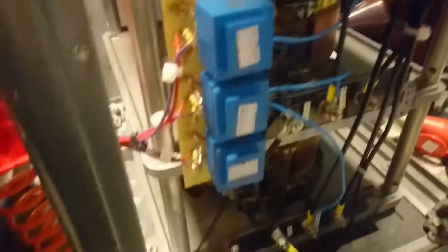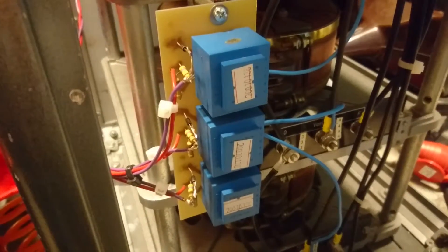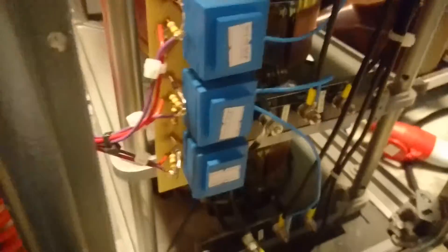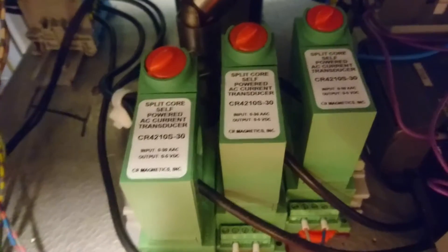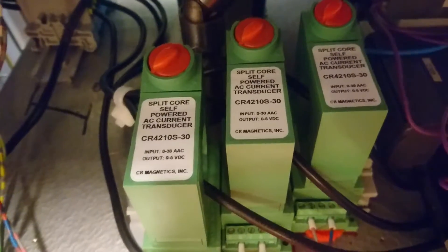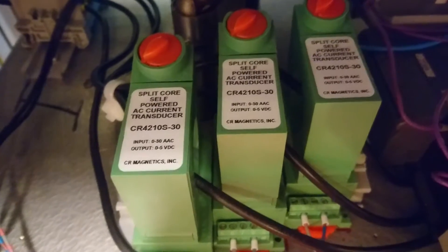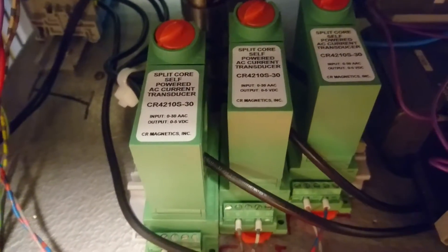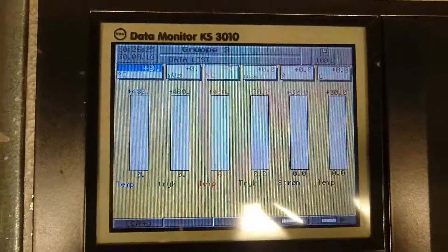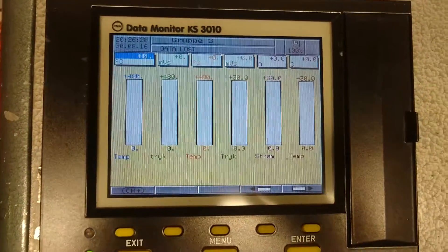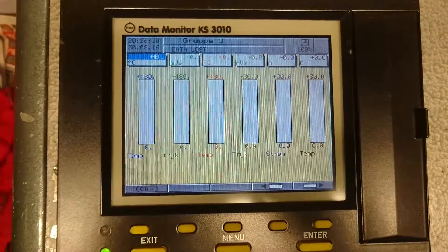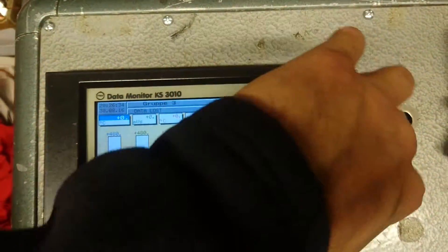I also added three step-down transformers to measure voltage between the three phases. And I also have up here three CR Magnetics AC RMS current to DC transducers. These voltage step-down transformers and current transducers are all connected to this PMA data monitor KS3010, which comes with a neat floppy disk drive for saving data.